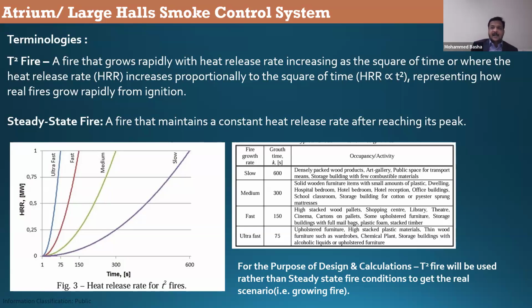T-squared fire. This is the actual fire that we will take into consideration for calculation or analysis purposes. T-squared fire means a fire that grows rapidly, with HRR, I call it HRR for heat release rate, increasing as the square of time, or where the heat release rate increases proportionally to the square of time. Let us take the second definition.